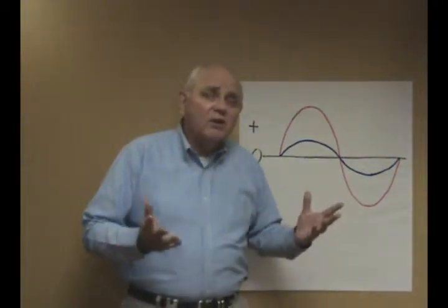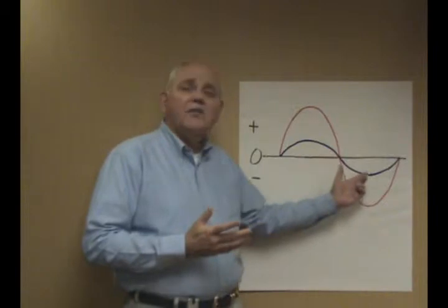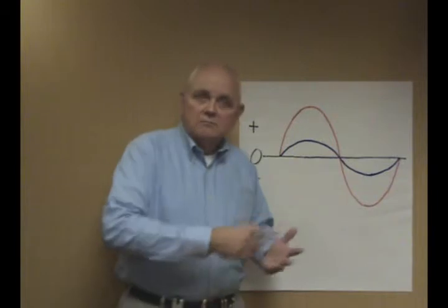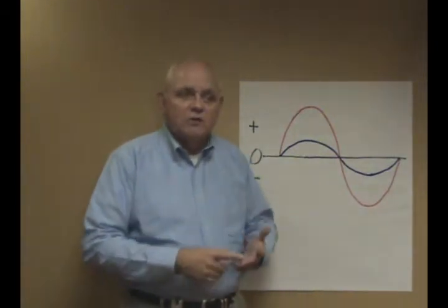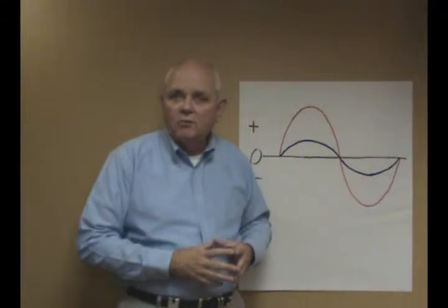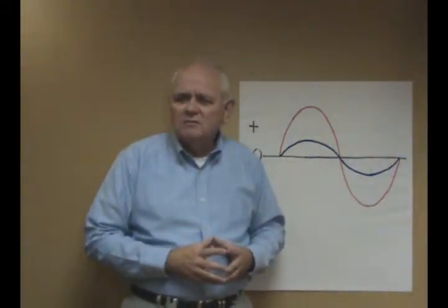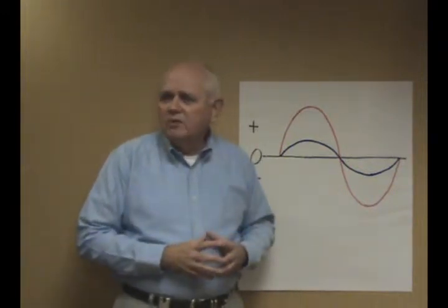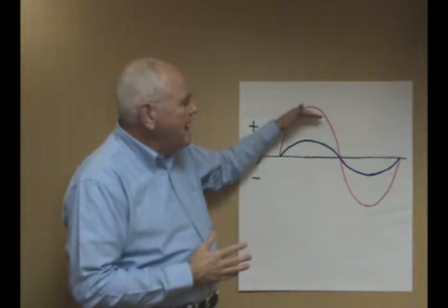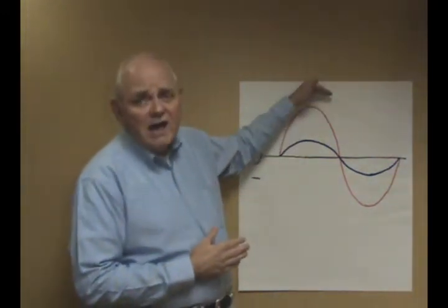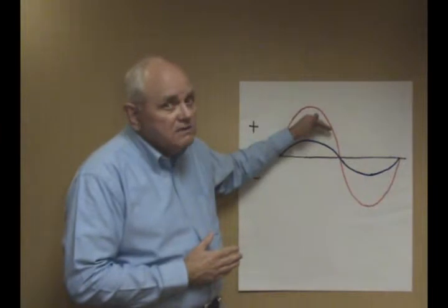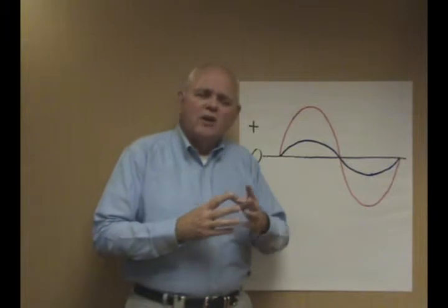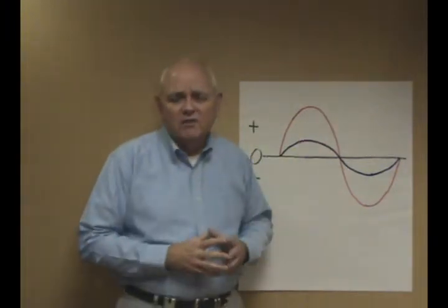Do we have any unwanted currents flowing in our system at frequencies other than 60 Hertz? Those we call harmonics. Harmonics can cause the neutrals to overheat, burn up transformers, burn up motors, distort our voltage sine wave, and cause us other problems as well. Are my voltages balanced from phase to phase? If not, I can destroy motors. Are the magnitudes of my voltages too high or too low? Lots of times if they're too low, I can end up burning up equipment. So in other words, do I have what we call swells and sags on our voltage levels?